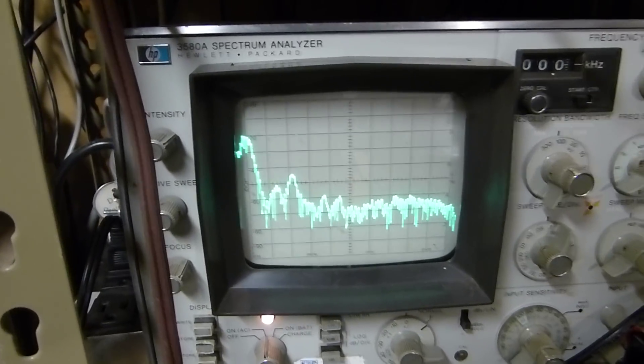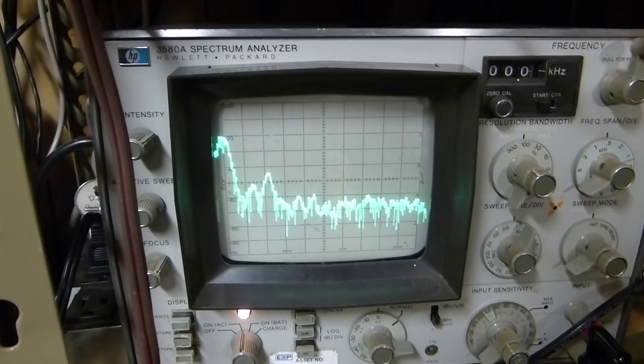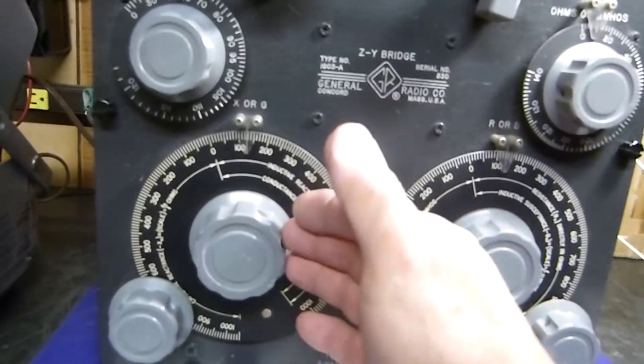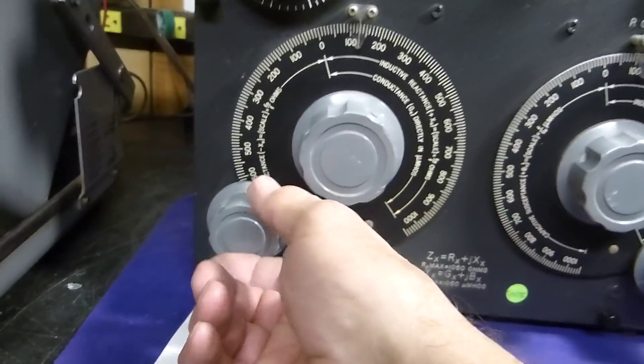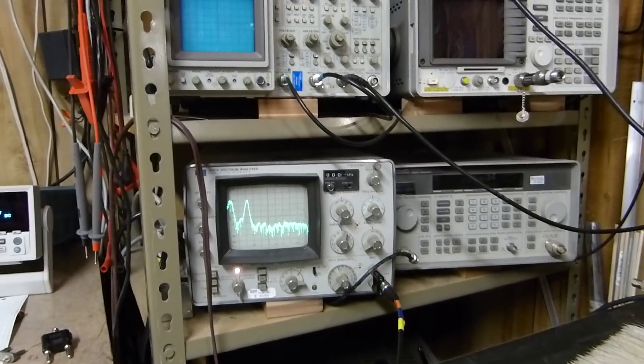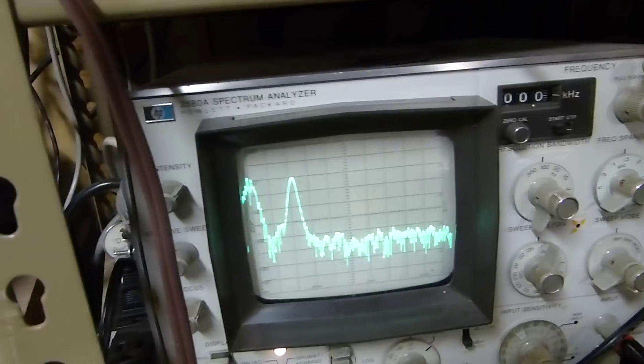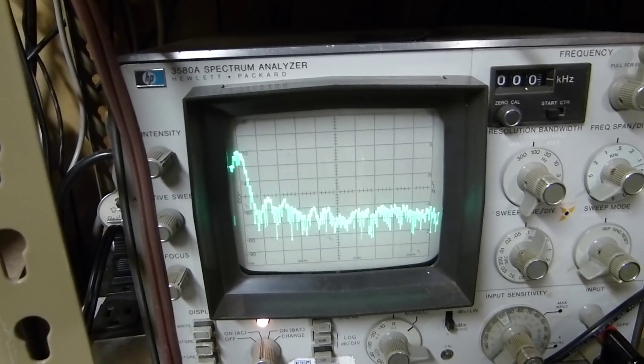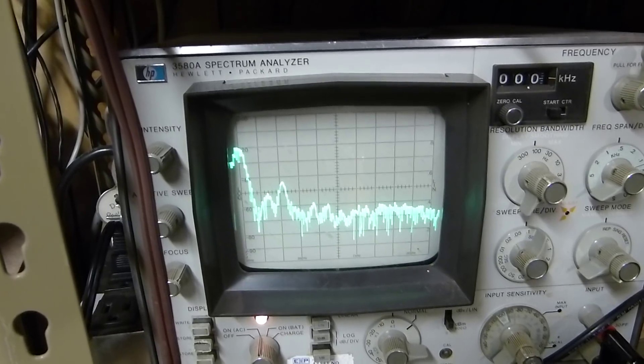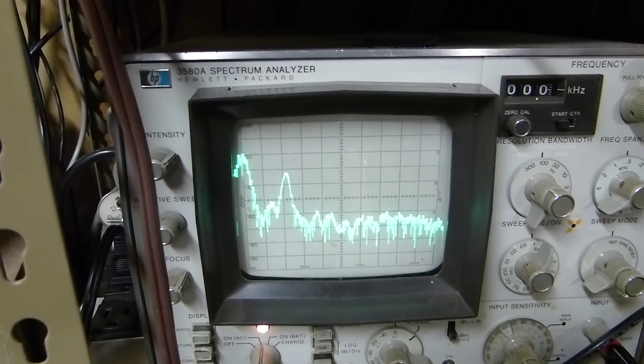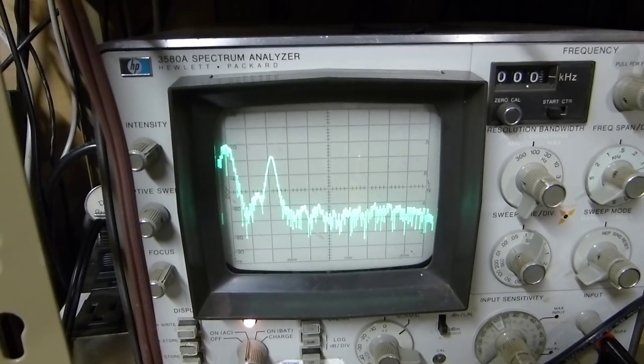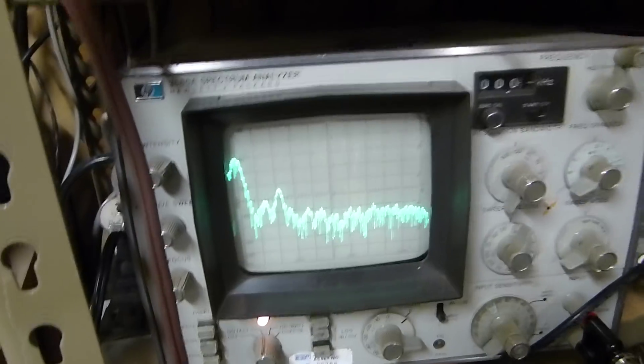See how it's sweeping there? You have to make an adjustment and watch for it to sweep. What we want to do is null this. When I turn these two knobs, here's the vernier for them, I'll turn it to throw it out of whack a little bit. See, we got another big pulse again. So we want to get this absolutely as close as we can. That's probably close enough.